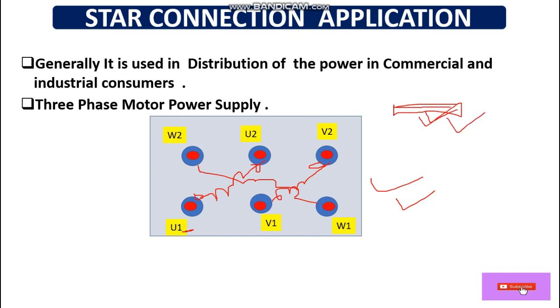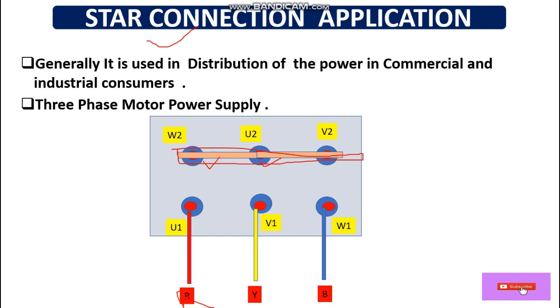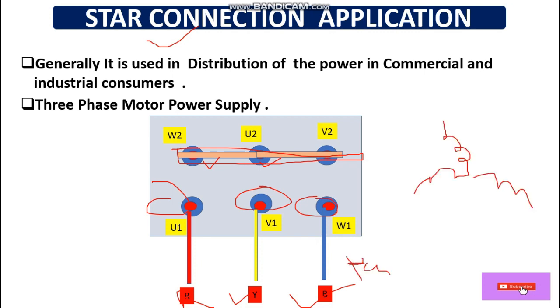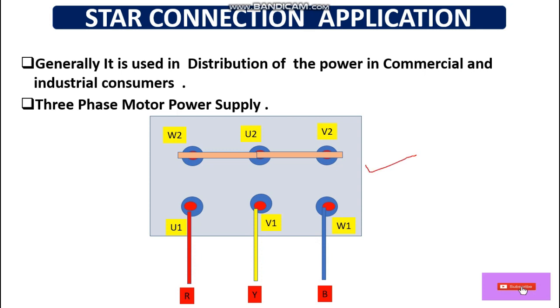To make a star connection in the motor terminal box, we use connector strips. Simply short all the second-end terminals — U2, V2, W2 — together at one point using a strip, then connect the three-phase power supply R, Y, B to U1, V1, and W1 respectively. In this way we can connect the motor in star connection.